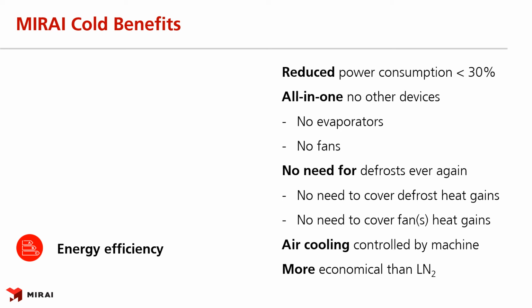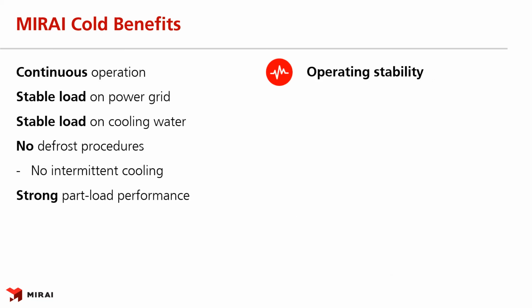And with that said, you probably know what it means. No more defrosts. No need to cover defrost heat gains or heat gains from ventilators. Also, air-cooled machines can be optimized for automatically controlled cooling of the machine to save energy. And as mentioned before, when running costs are considered, air is more economical than liquid nitrogen. Air cycle machines have a great key benefit in the form of stable operation. There are no sudden energy peaks required by the system's demand for cold. So in conclusion, Mirai Cold is very gentle with the power grid and cooling water demand. Since there are no defrost procedures necessary, this also contributes greatly to the operating stability.